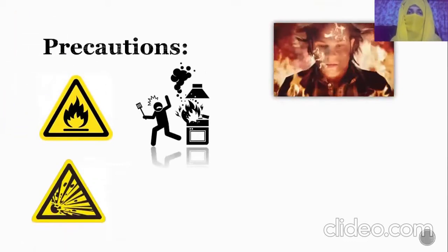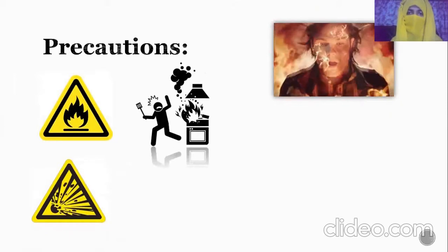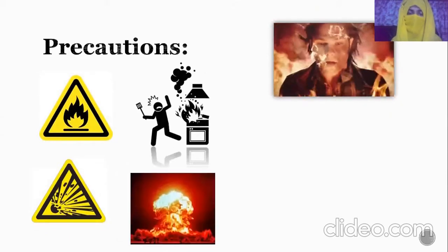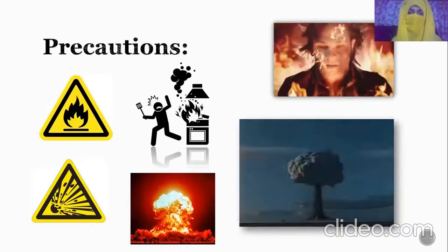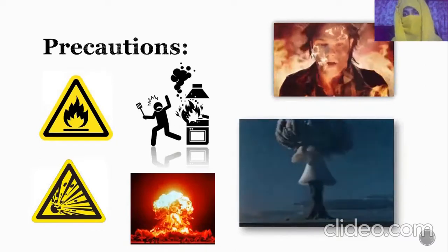Precautions: do not extend your hand over the bomb calorimeter. It can cause burning. Do not fire the bomb if it is tilted or if there is any evidence of gas leakage. It can cause an explosion if the reaction goes out of control. So the explosion can be serious.